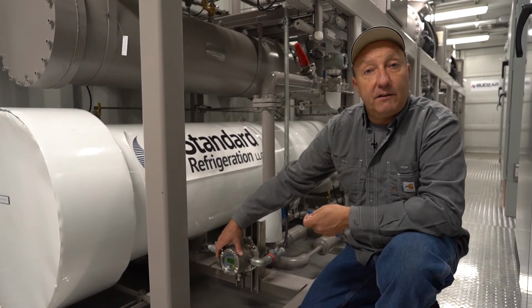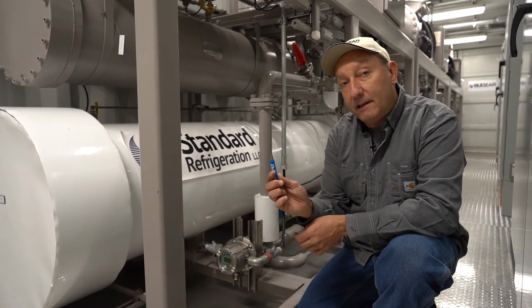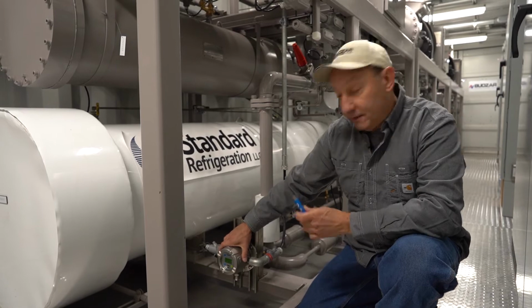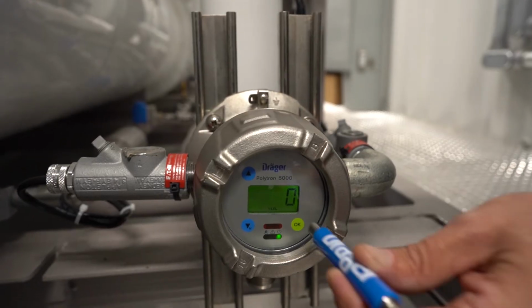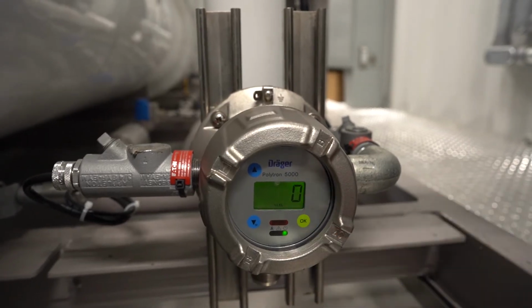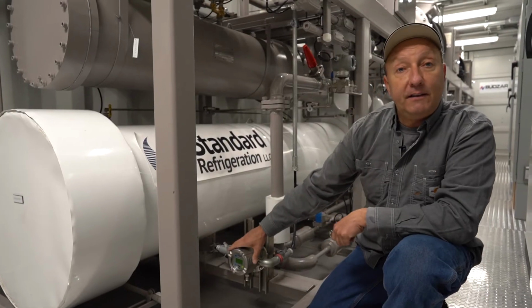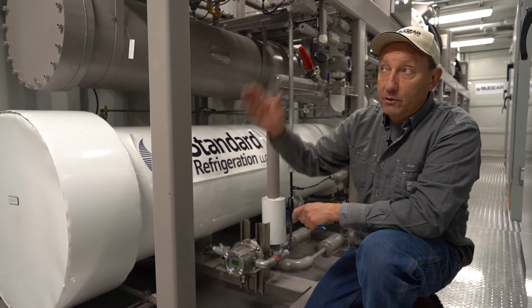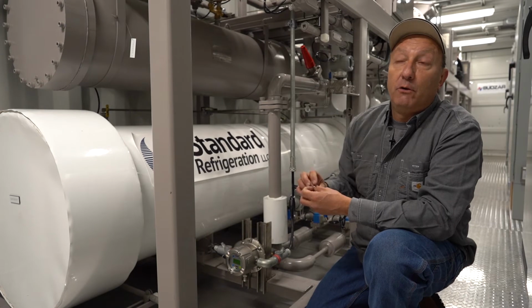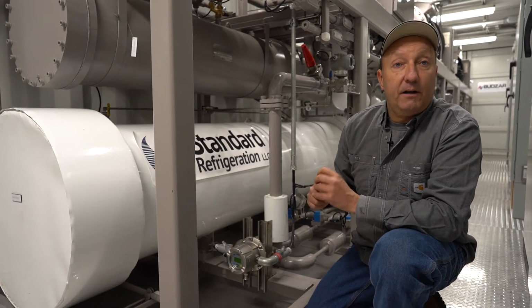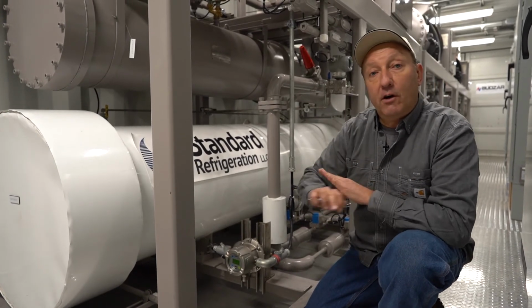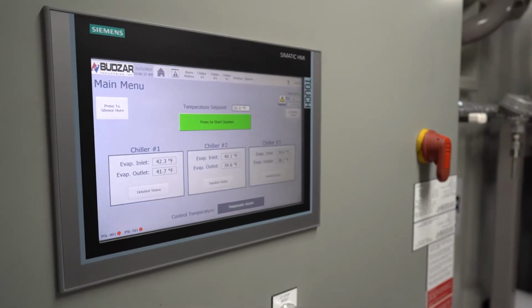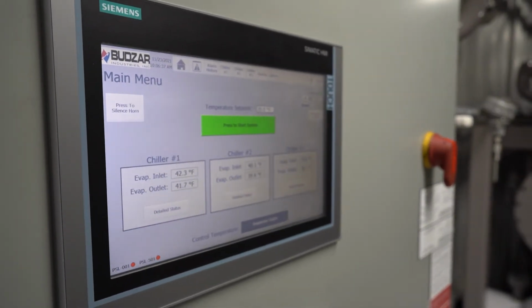Once it goes back down to 0, you have to use a magnet, because it's an explosion-proof device, to reset the device. You simply place the magnet by the OK button. It will reset the device locally, and then you go to the HMI in the main control panel and acknowledge the alarm there as well. That will shut off all the audible and visual alarms, and you'll be able to go back to running.